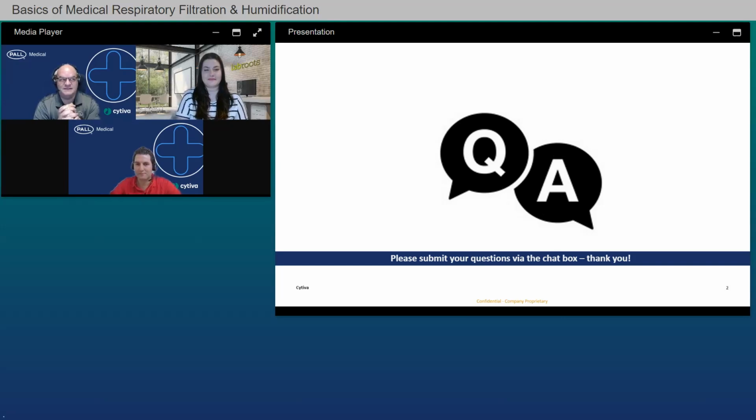BB100. It's the ICU filter, and as I said, if you design a filter, it's always a trade-off between size, weight, humidification, filter efficiency, and handling. In general, the filter efficiency is the same with all of our filters. The other conditions, like the size, for example, added dead space, what I talked about earlier, depend on the application.